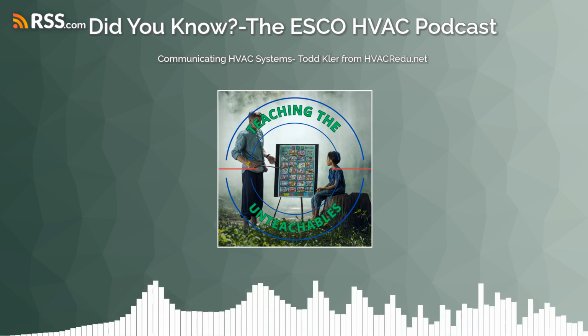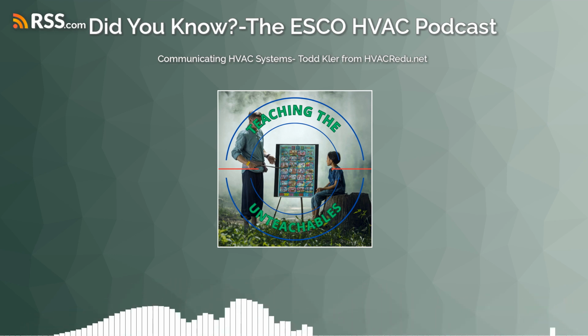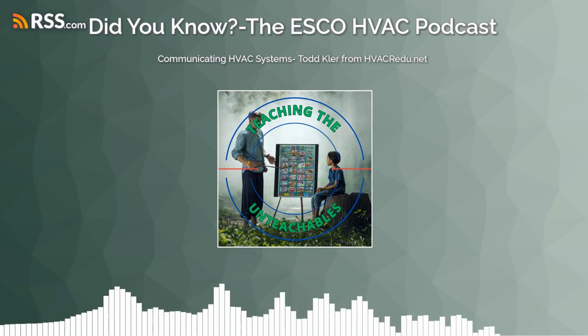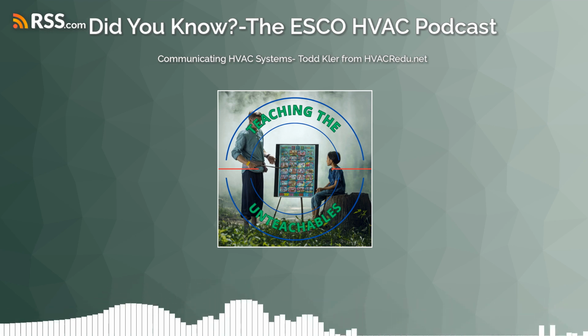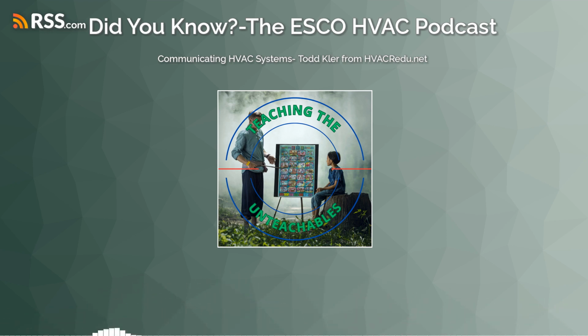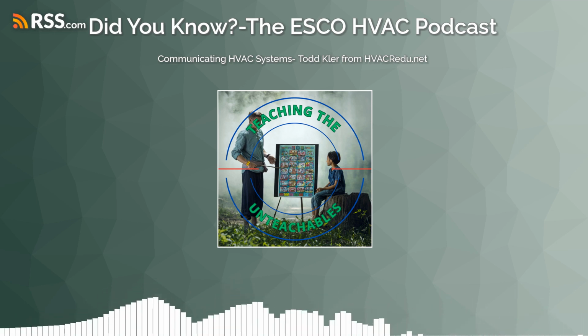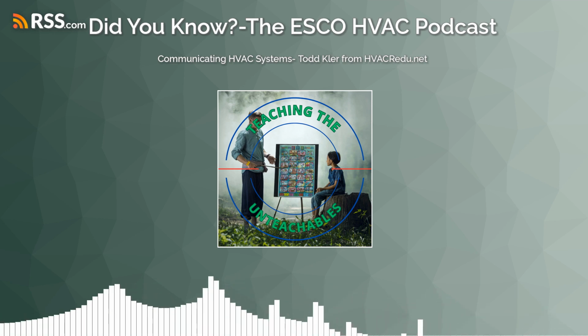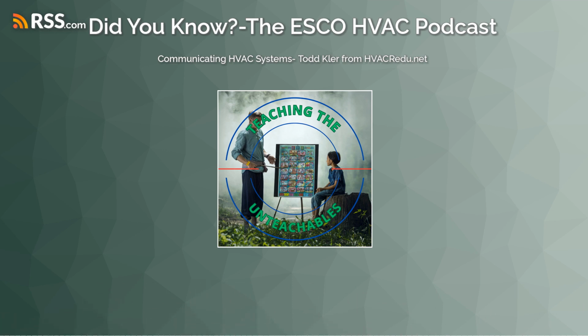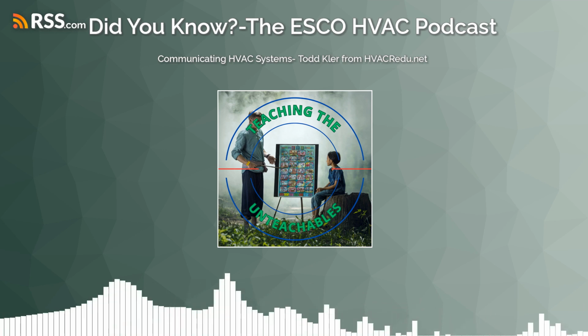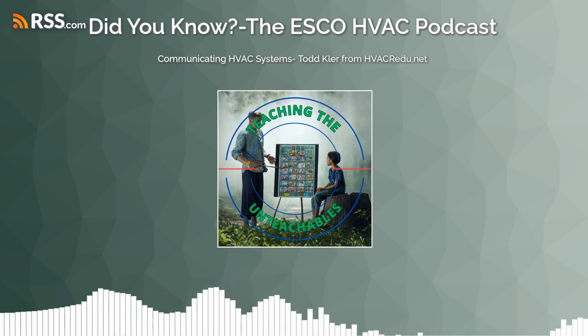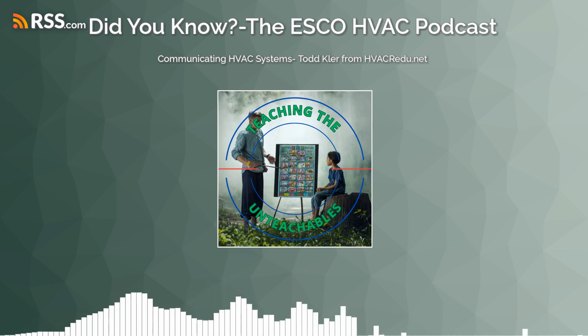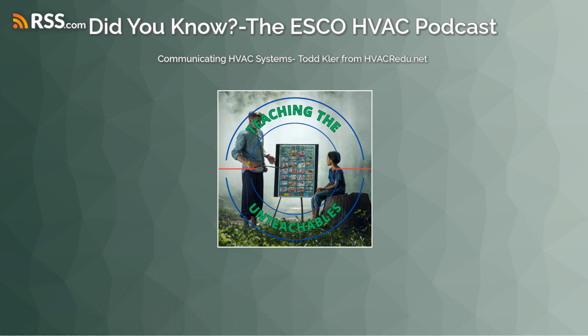Data? Right. In our indoor unit, it might call them A, B, C, and D, but then all we got to do is look at the wall controller, or we look at the outdoor unit, and we see exactly what those things are. So I see 24 volt hot between common and D or R. And then I see a negative communicating signal on B or DX negative and a positive on A. Looks pretty dang familiar. I wonder if we can check this one. Well, why not? Look at that.